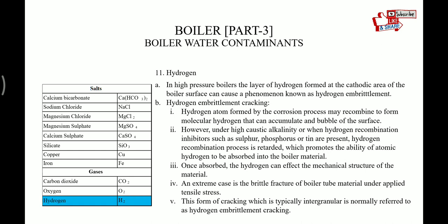In high pressure boilers, the layer of hydrogen formed at the cathodic area of the boiler surface can cause a phenomenon known as hydrogen embrittlement cracking. Hydrogen atoms formed by the corrosion process may recombine to form molecular hydrogen that can accumulate and bubble off the surface. However, under high caustic alkalinity, or when hydrogen recombination inhibitors such as sulfur, phosphorus, or tin are present, the hydrogen recombination process is retarded. This promotes the ability of atomic hydrogen to be absorbed into the boiler material. Once absorbed, the hydrogen can affect the mechanical structure of the material. In an extreme case, brittle fracture of the boiler tube material can occur under applied tensile stress. This form of cracking, which is typically intergranular, is referred to as hydrogen embrittlement cracking.